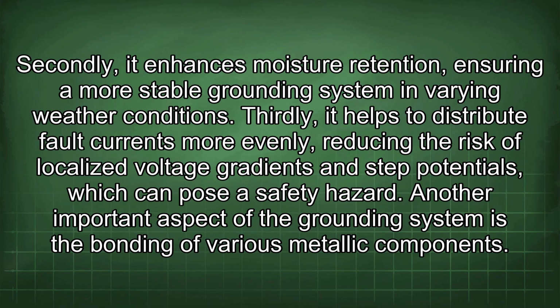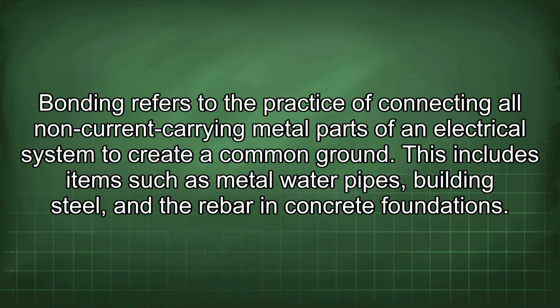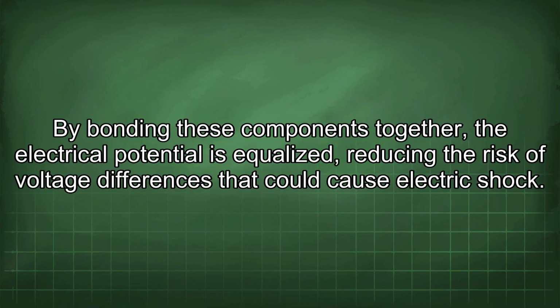Another important aspect of the grounding system is the bonding of various metallic components. Bonding refers to the practice of connecting all non-current carrying metal parts of an electrical system to create a common ground. This includes items such as metal water pipes, building steel, and the rebar in concrete foundations. By bonding these components together, the electrical potential is equalized, reducing the risk of voltage differences that could cause electric shock.